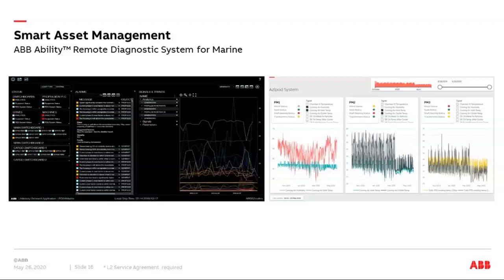In the middle section, you have a very detailed event list where you have access to information in the resolution of milliseconds. So much more detailed than, for example, your traditional automation system or HMI system. In addition to displaying any kind of alarm, event, fault, or even parameter changes that occur inside any of the monitored equipment, it also gives the operators or the crew on board access to troubleshooting advice. So every fault that can occur is always linked with hints for rectification, what can be done to rectify the fault or the problem that has occurred, and it also indicates possible causes. To give you an example, if a frequency converter trips out on an overcurrent fault, it will immediately give the electrician or the engineers on board information on where to start the troubleshooting process.